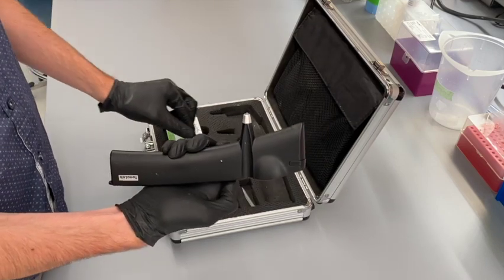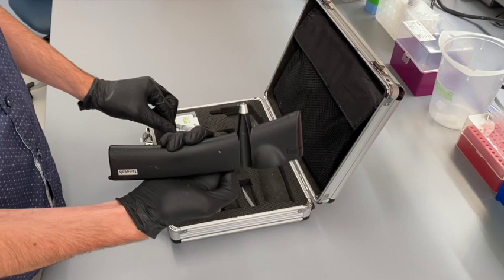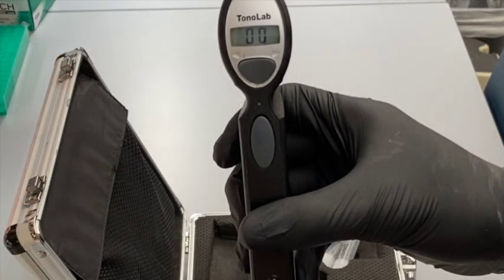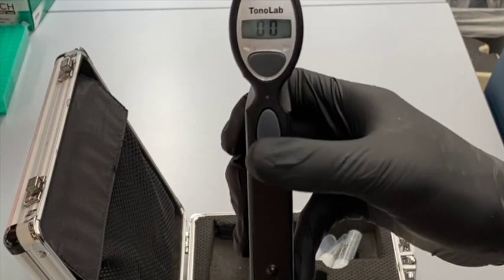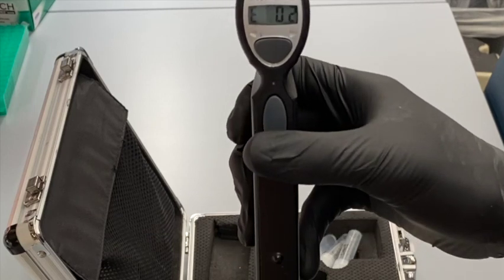Once the probe has been placed inside, you will hit the back button again in order to zero out the reading. That same button on the back of the TonoLab, pressed to accept that the probe has been inserted, is used to perform most of the functions of the TonoLab as well. For example, that is how you take a reading. If you push that button without the TonoLab being prepared to take a reading from an animal, then you will get an error symbol, as you can see here.